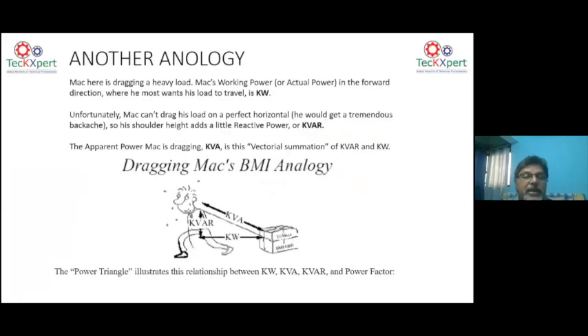A simple analogy for reactive power is a person who is pulling a load, as you can see, and the load is moving horizontally. The active power used is to shift the load on a horizontal plane, and for that purpose, the person has to lift the rope and pull it. By doing that, a certain amount of energy goes into the kVAr, which is the shoulder height, and the horizontal distance the load is moving is the actual work produced by the pulling effect.